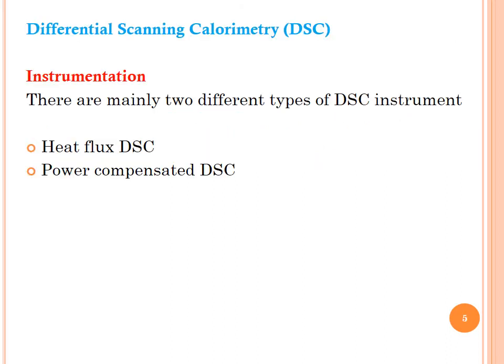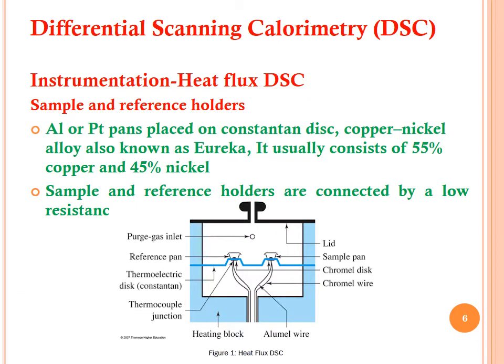Let's discuss the instrumentation of DSC. There are mainly two different types of DSC instruments: heat flux DSC and power compensated DSC. In the heat flux DSC, the components include sample and reference holders — aluminium pans placed on a constantan disk. Constantan is a copper-nickel alloy, also known as Eureka, consisting of 55% copper and 45% nickel. Sample and reference holders are connected to a low resistance.